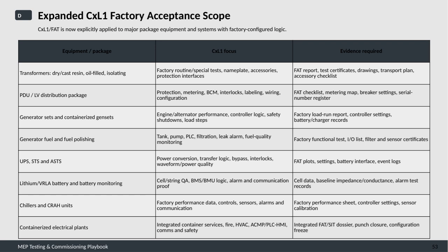For generator fuel systems and fuel polishing units, components such as tanks, pumps, PLC controls, filtration, leak alarms, and fuel quality monitoring are tested functionally in the factory. Evidence here involves functional test reports, input-output lists, and filter and sensor certificates. Uninterruptible power supplies, UPS, static transfer switches, STS, and automatic static transfer switches, ASTS, are assessed on power conversion efficiency, transfer logic, bypass functionality, interlocks, and waveform or power quality. Supporting evidence includes FAT plots, settings, battery interface records, and event logs.